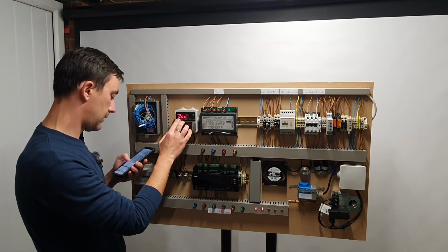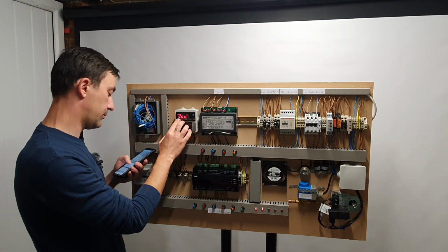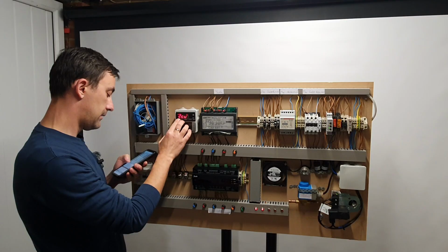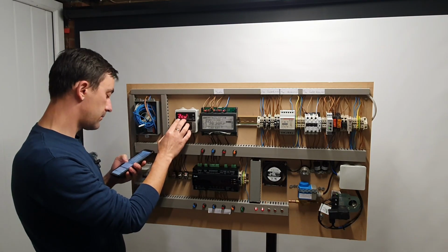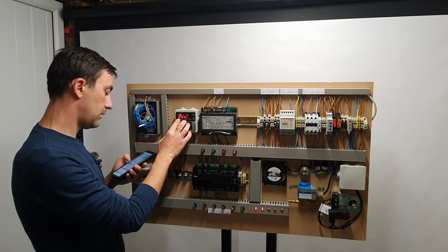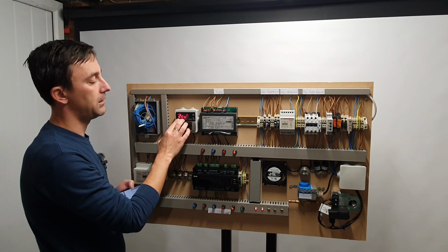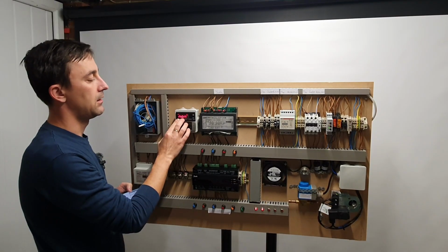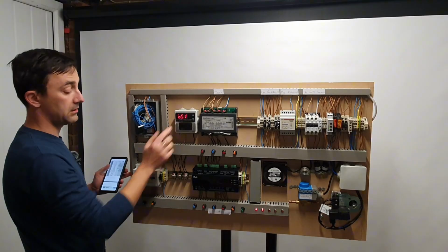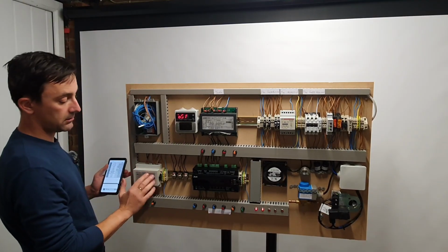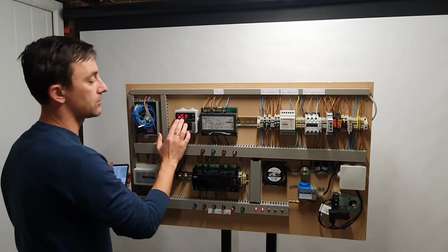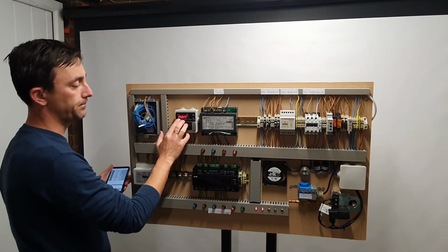OAU is set to control of auxiliary outputs. So this one you can say as an alarm, as light, also you can set it as 2CU, being a second compressor, but it does not have this option. The parameter is there, but it's not physically present on the controller. So that's why we're just gonna set this as none.